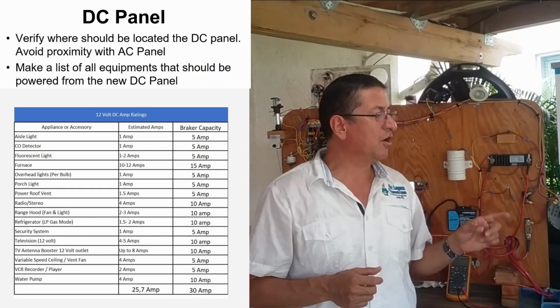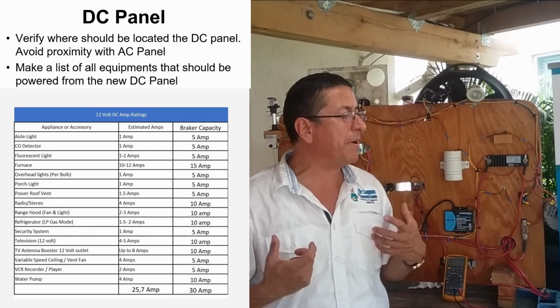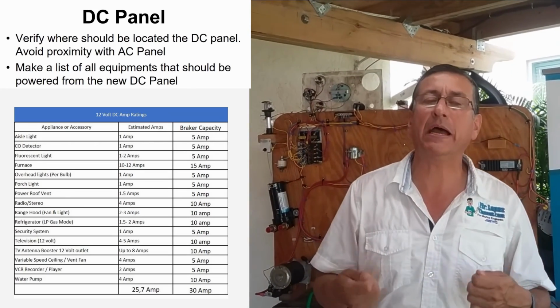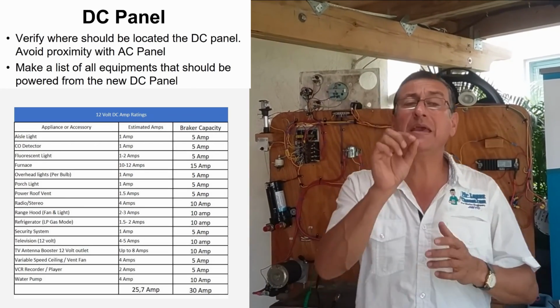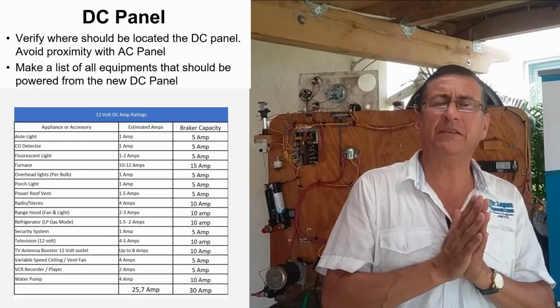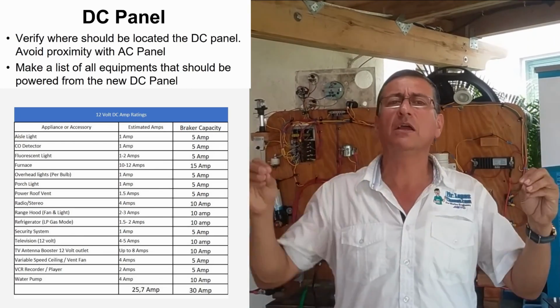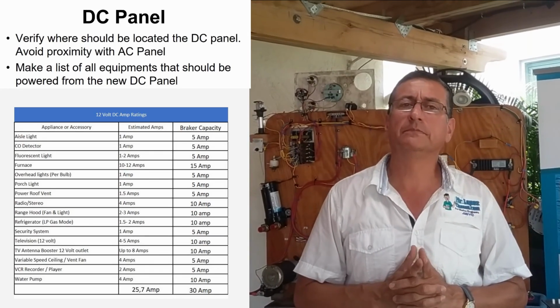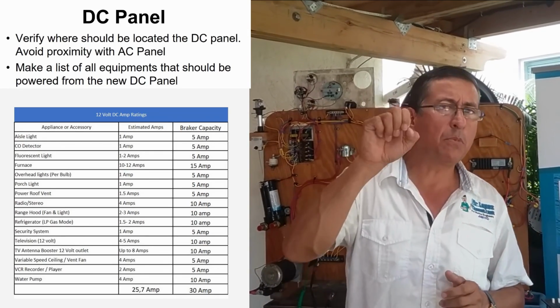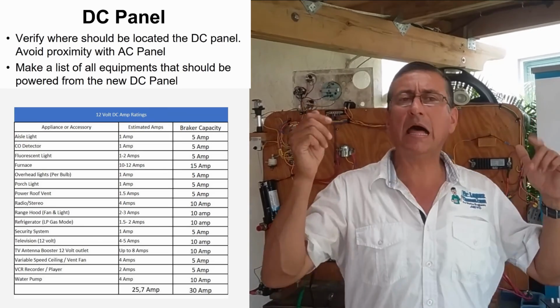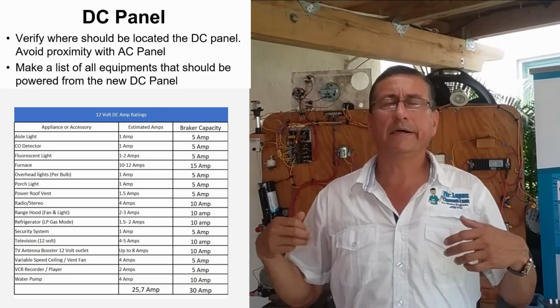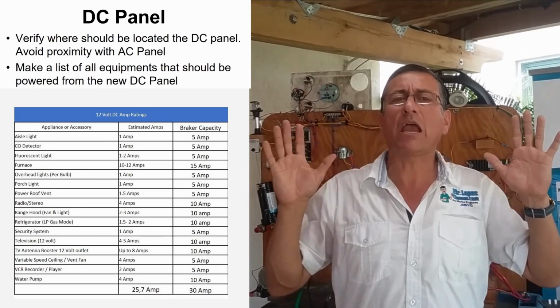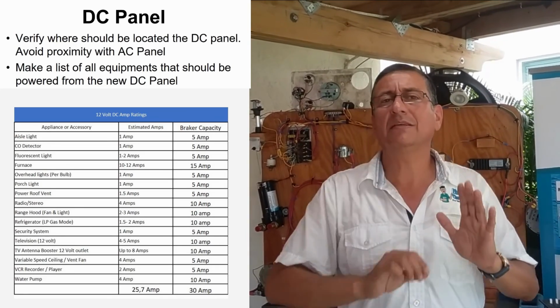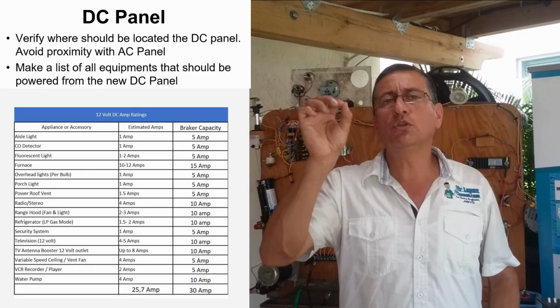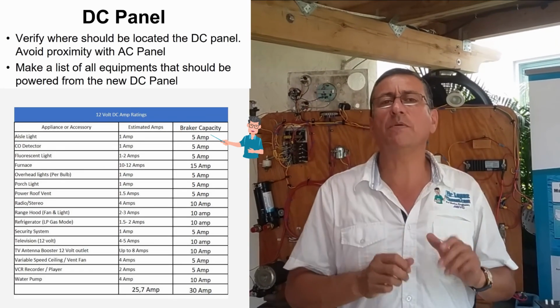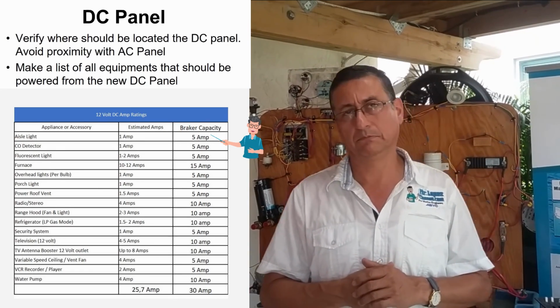Make a list of all equipment that should be powered from the new DC panel. What does that mean? You need to list all the equipment that we are going to connect together on the DC panel - for example, 5 blowers, lights, all the DC equipment. Make a list, and next to each item put the capacity of each equipment in amps per hour.